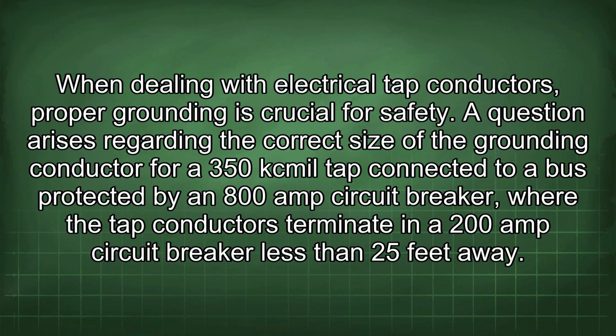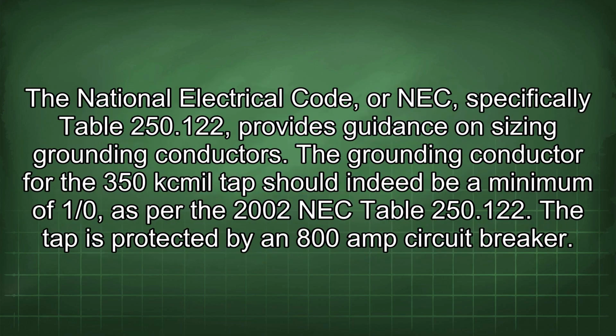When dealing with electrical tap conductors, proper grounding is crucial for safety. A question arises regarding the correct size of the grounding conductor for a 350 kcmil tap connected to a bus protected by an 800 amp circuit breaker, with the tap conductors terminating in a 200 amp circuit breaker less than 25 feet away. The National Electrical Code, or NEC, specifically Table 250.122, provides guidance on sizing grounding conductors.